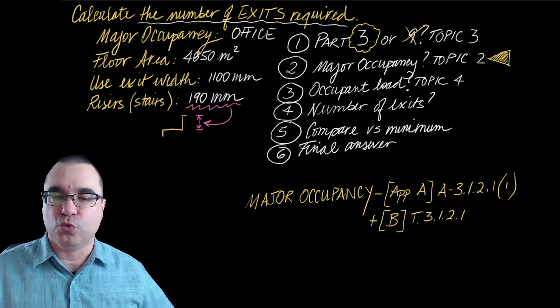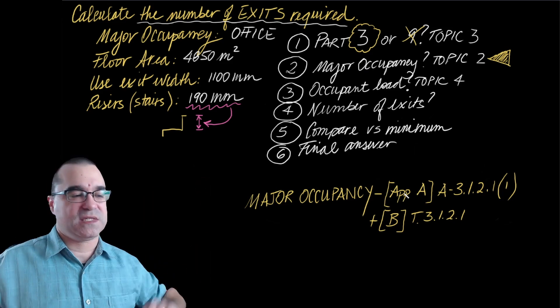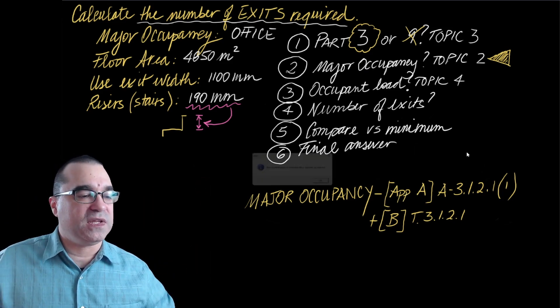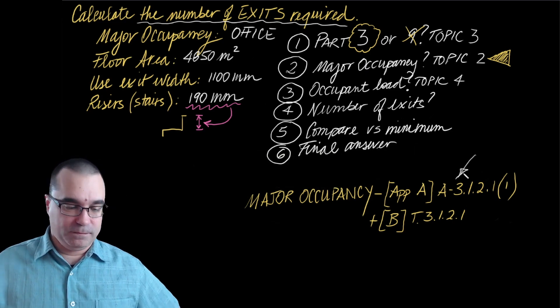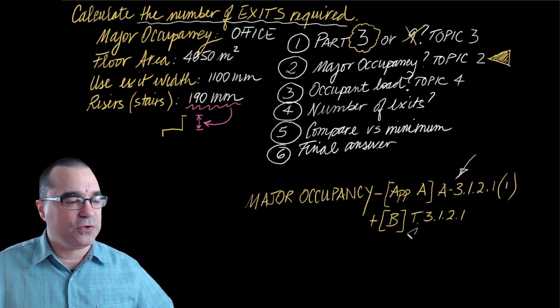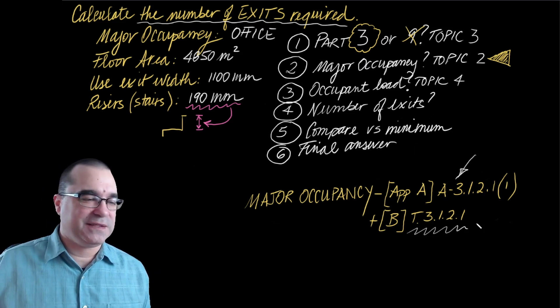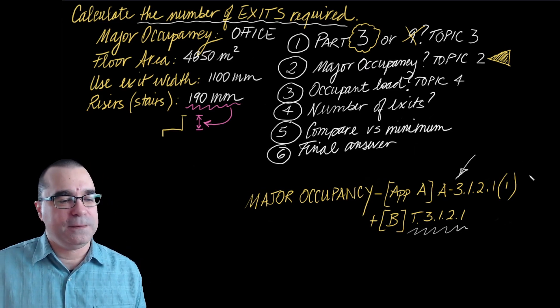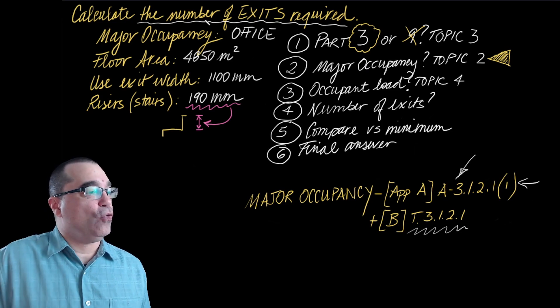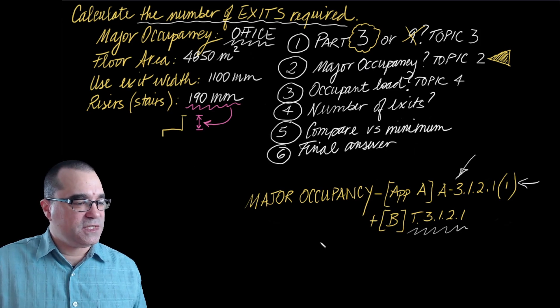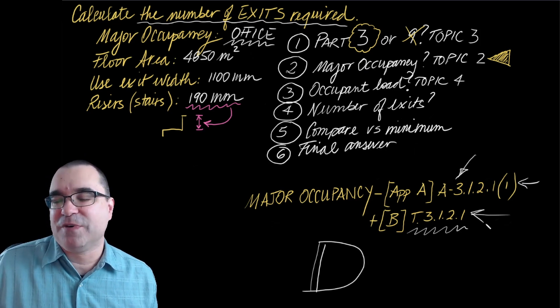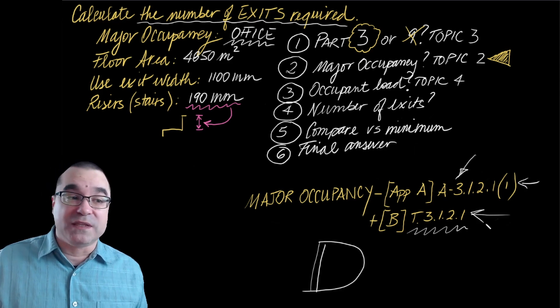We can now move on to step number two. Under step number two, we're going to use what we learned in topic two to identify the major occupancy for this building. Start with appendix A to identify what the group and division as necessary is for this building, and then go to table 3.1.2.1 to find out what the name of that major occupancy is. So I went to appendix A under sentence 3.1.2.1, and I found that for an office building, the major occupancy is D. And then when I go to table 3.1.2.1, I find that the name of that major occupancy is business and personal services. Great. We're done with step two.